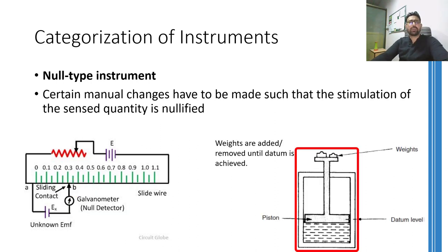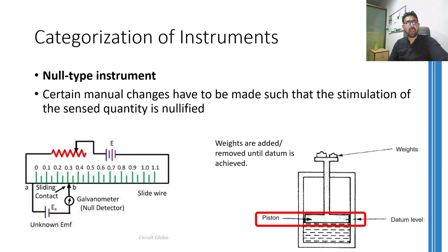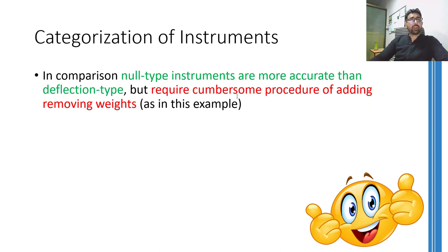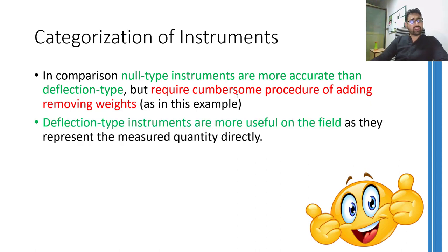Another example of null type instrument is a pressure measuring instrument shown in this schematic. The pressure of the fluid will raise the platform above the datum point. Therefore, downward force is applied on the piston by placing some weights on it. If the downward force applied by the weights become equal to the force applied on the piston by the pressurized fluid, then the piston will be at datum point. At this moment, the amount of weight will be directly proportional to the pressure of the fluid. Normally, null type instruments are much more accurate than deflection type instruments and therefore are used for calibration purposes. Note that deflection type instruments are easier to use and therefore are installed at suitable locations in any factory floor, whereas null type instruments are cumbersome to use and therefore are seldom used on the factory floor.